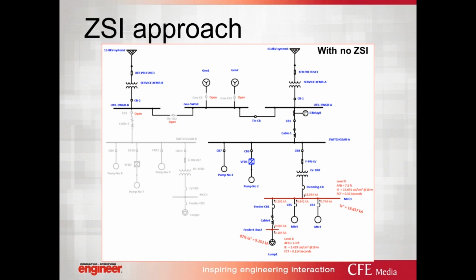Now, based on the information, the calculation of incident energy for this point, based on almost 0.33 seconds, is 15.7 calories per centimeter squared. Remember, we try to coordinate this incoming breaker with the load feeder breaker to make sure the coordination exists. At the same time, we are penalizing ourselves, which again we don't have a choice about, by almost 0.33 seconds time delay FCT for getting this incident energy.